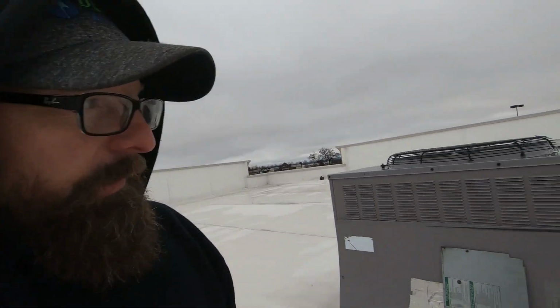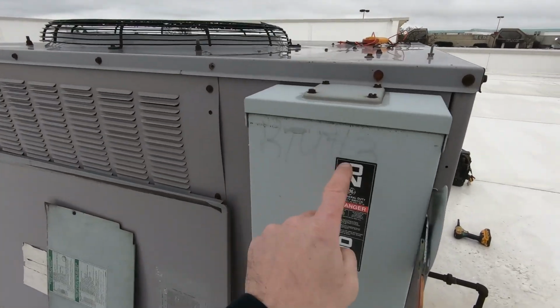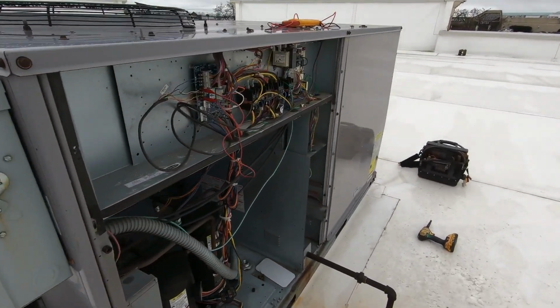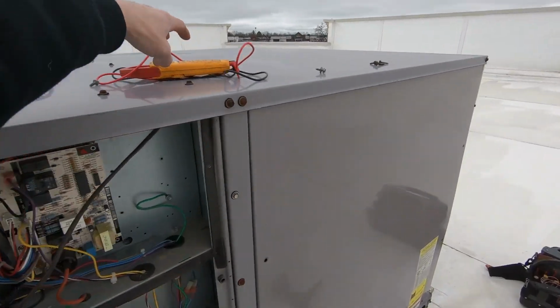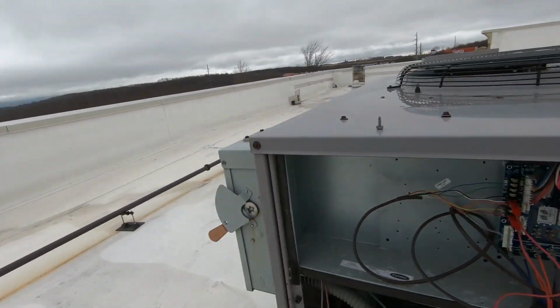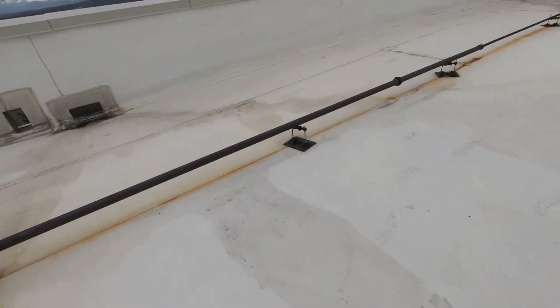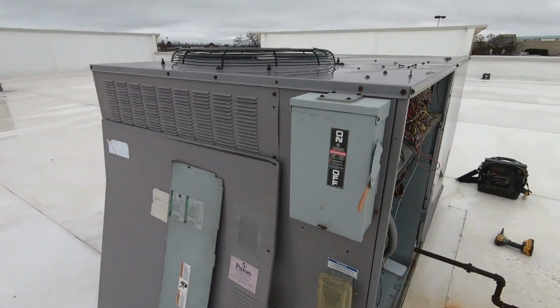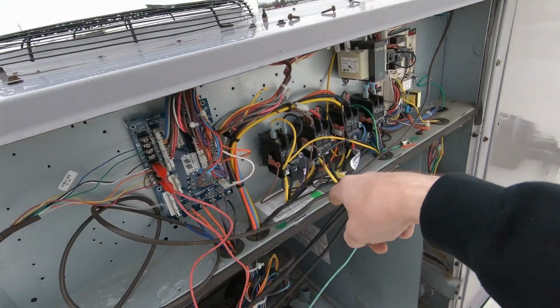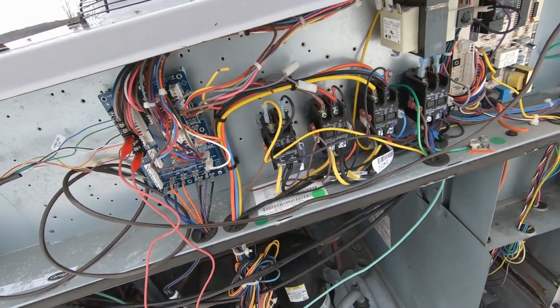I thought maybe the breaker was tripped and we had some other major issues, but I don't think so. I tested everything to ground to see if it was shorted to ground. See, this one's marked RTU2, but the breaker was marked RTU1 in the panel. So I'm just gonna confirm that there's power real quick. I'm sure there is. And we'll go from there. And like I said, I tested everything right here to ground.